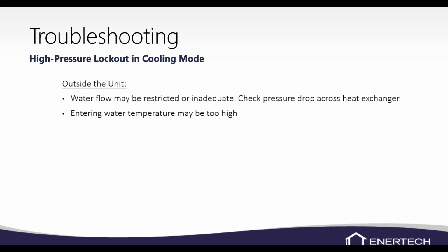And it could be a problem with the loop field itself. Maybe one of the vertical wells or the horizontal loops is airlocked and we're not moving water flow through it. So, if it hasn't been super hot for a long period of time, but they're still running high temperatures, then we need to look more into that loop field, and we may need to flush that loop field again.